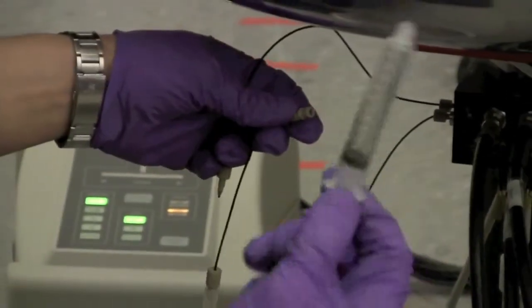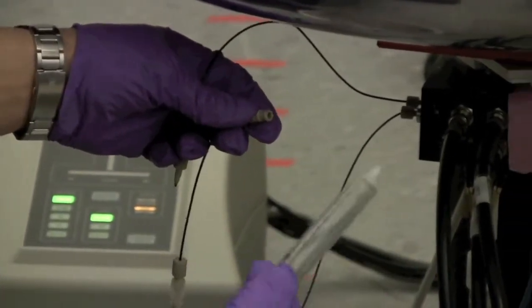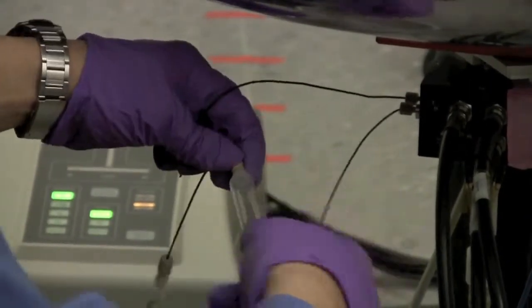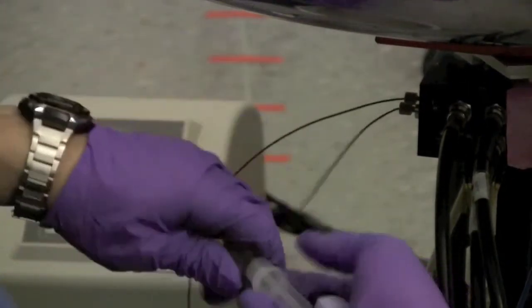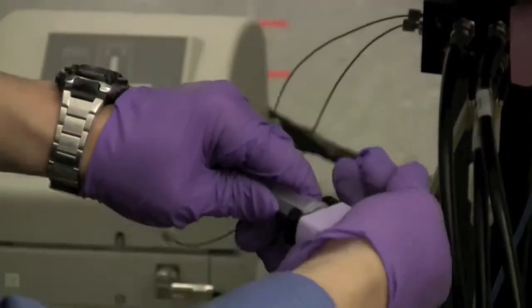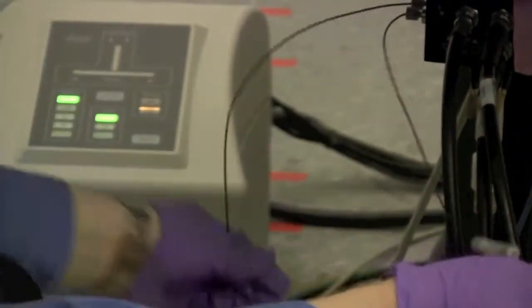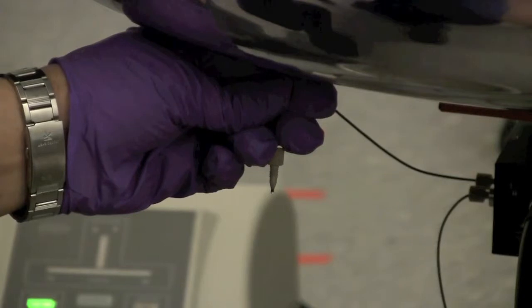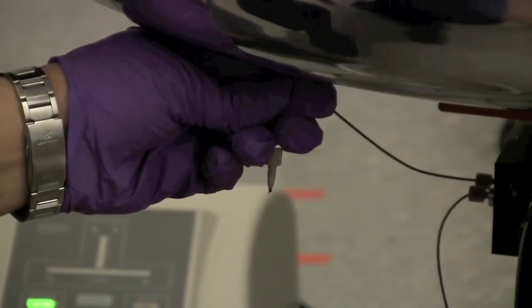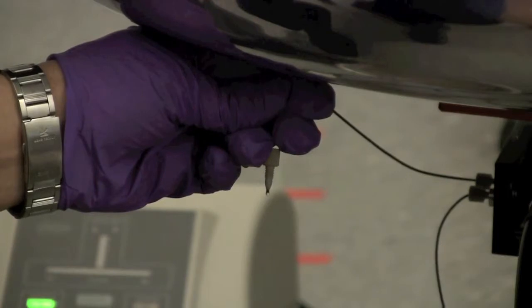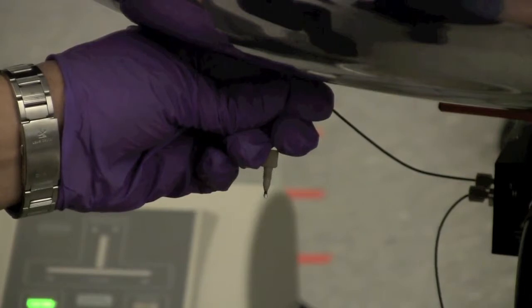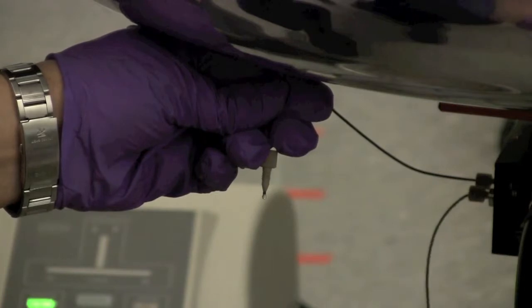So I'm going to attach the big syringe again. Make sure, remember to draw it up before you attach it. And then I'm going to push it down and lock it into place. And we're going to watch the acetone come out. There you can see the bubble starting to form, and it will slowly push its way through the probe. You need to wait until the air has pushed the acetone completely out of the probe, and you can tell because the bubbles stop growing on there and air starts flowing out of the end of the capillary.